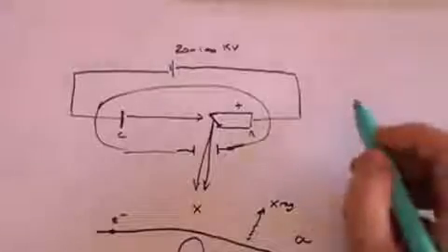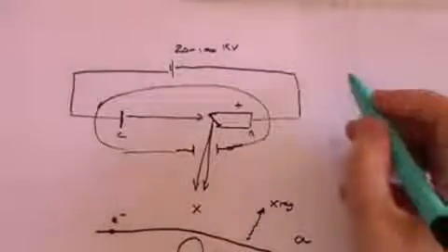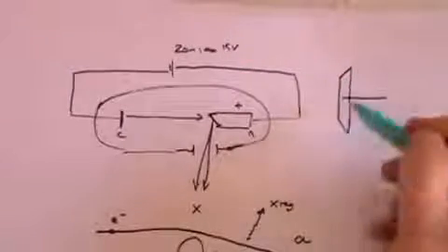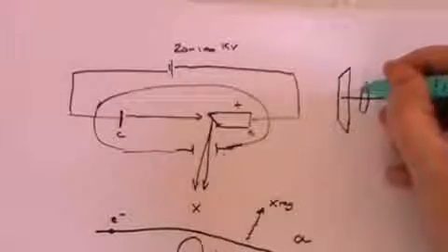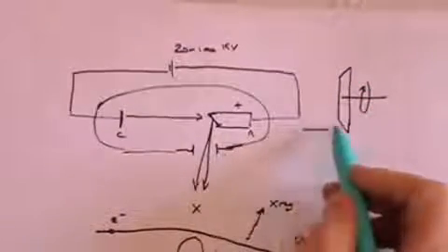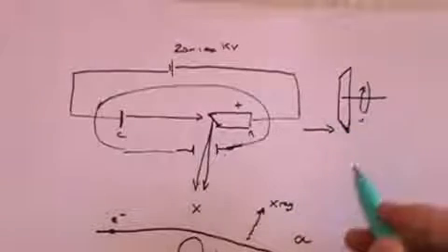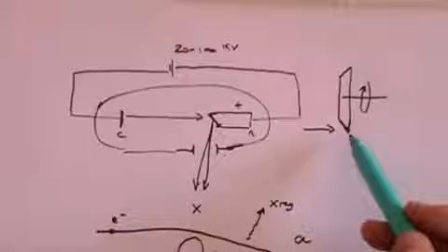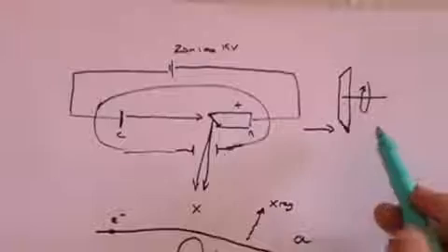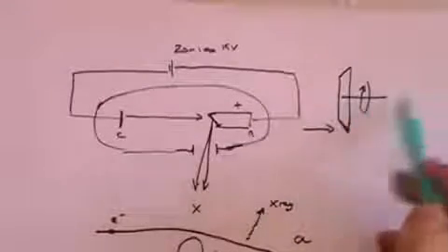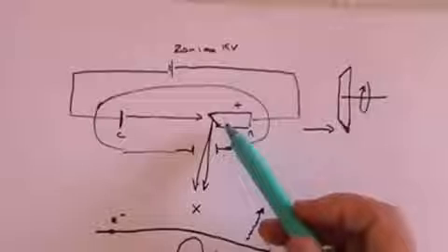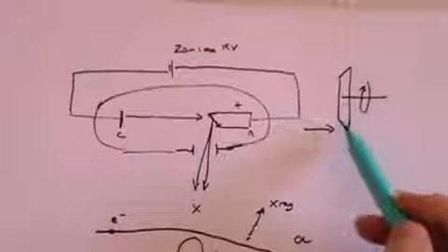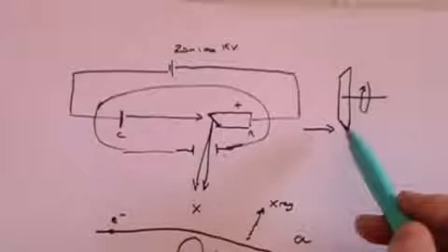So what you tend to find is that the anode is shaped as a circular disc, and it's constantly spinning, so it's spinning kind of on this axis. The electrons are hitting the slanted part of the anode there, but because it's spinning, not one single point is being constantly heated, and quite often there's a means of getting that heat to move away. If you simply had an anode like this, it would probably melt. But if you spin it around an axis, so this is constantly changing, then there's a way of keeping it cool.